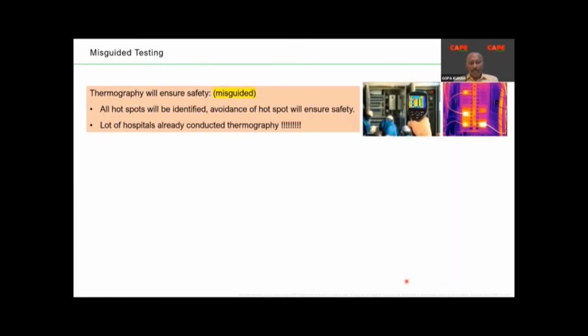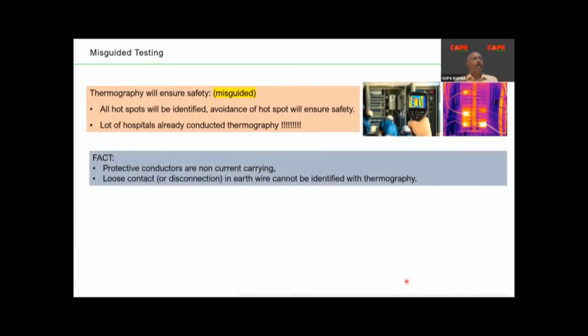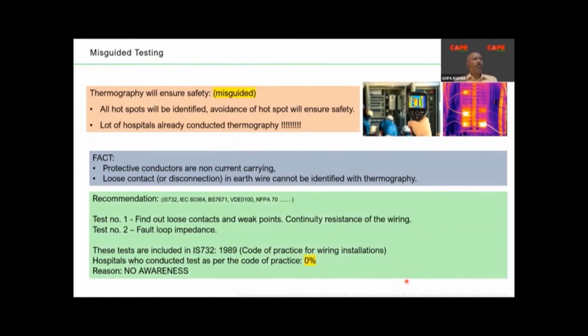Now in hospitals, what I have seen in a lot of places is that people are misguided by thermography. A lot of engineers think that by doing thermography, electrical safety can be achieved. This is absolutely wrong. So far in the IS and IEC standards which I am referring to, thermography is not considered a mandatory test which can ensure safety. Of course, you will get beautiful pictures and you can find out whether any loose contacts are there. But there are much more efficient tests already included in the standard. You must do those. Probably thermography can be done as an additional safety measure. In my points 14 and 15, I have put the inspection and testing. Over and above that, you can do thermography, but doing only thermography can never ensure any safety in your wiring.